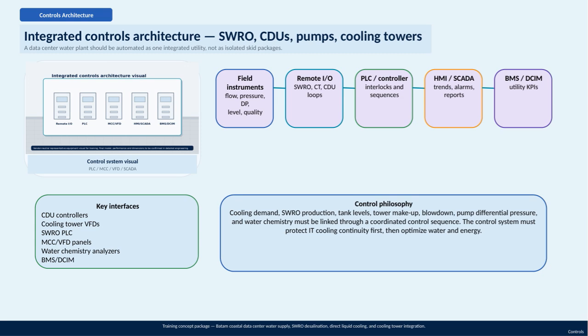The main idea here is that the entire water system, including the seawater reverse osmosis units, cooling distribution units, pumps, and cooling towers, should be managed as one integrated utility rather than as separate, isolated components. This integration ensures seamless operation and better resource management. Our training package focuses on this integration, covering water supply, SWRO desalination, direct liquid cooling, and cooling tower coordination.